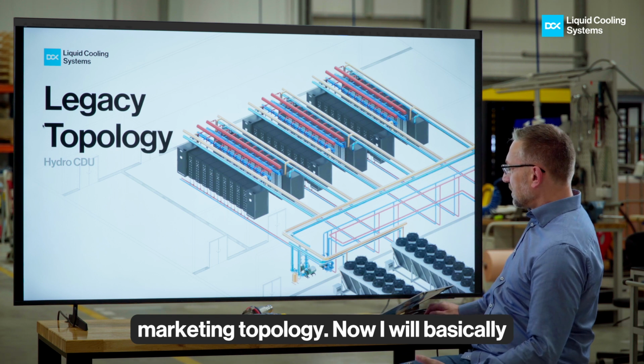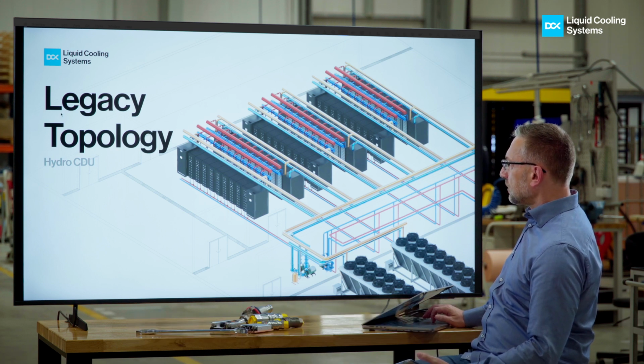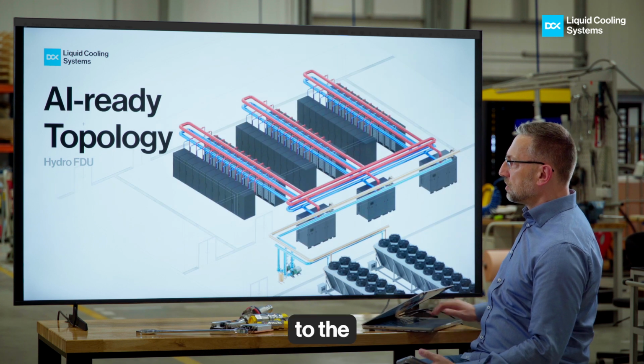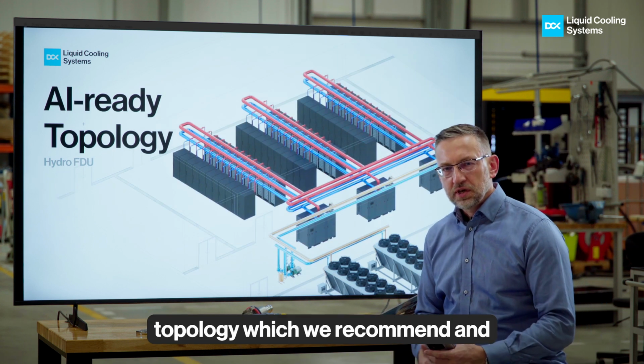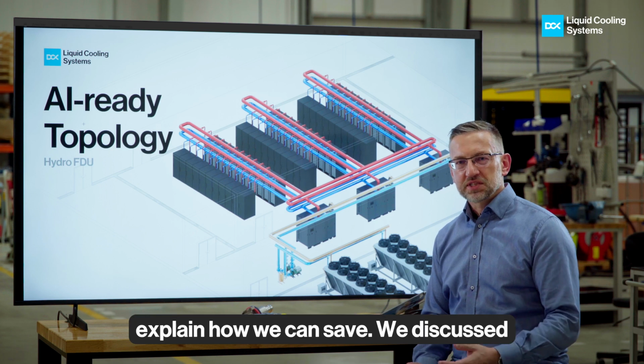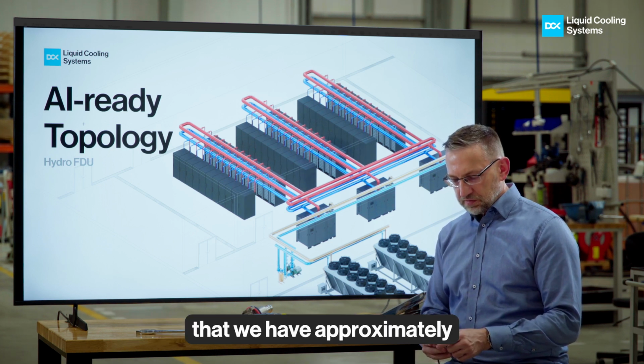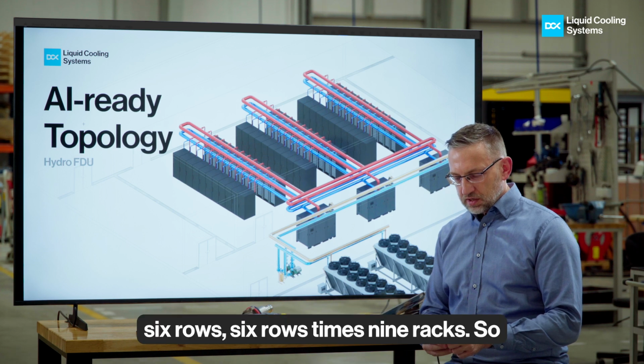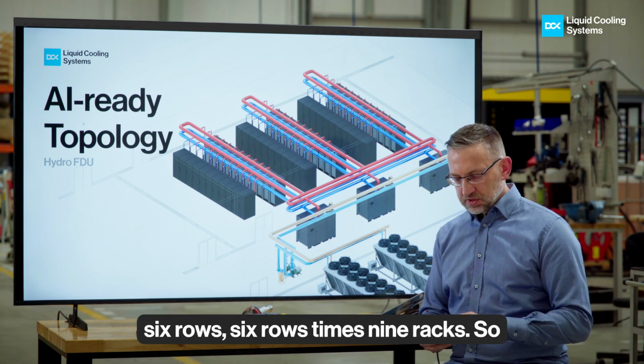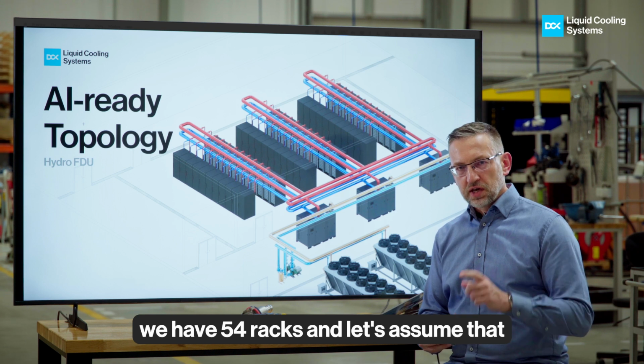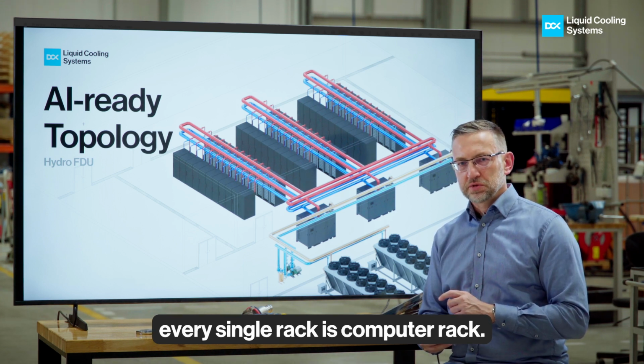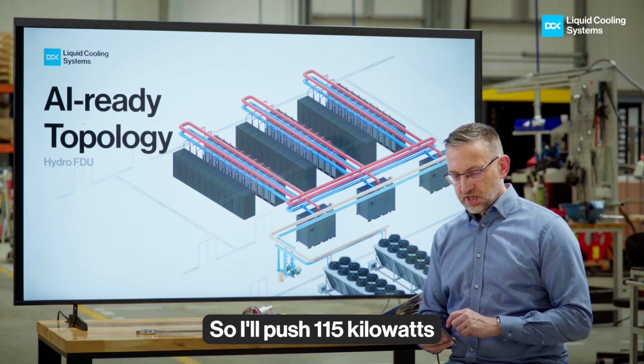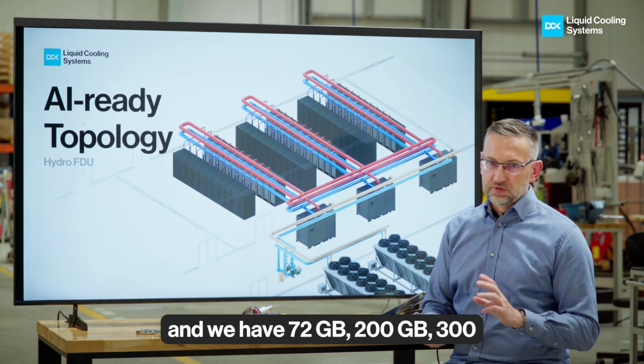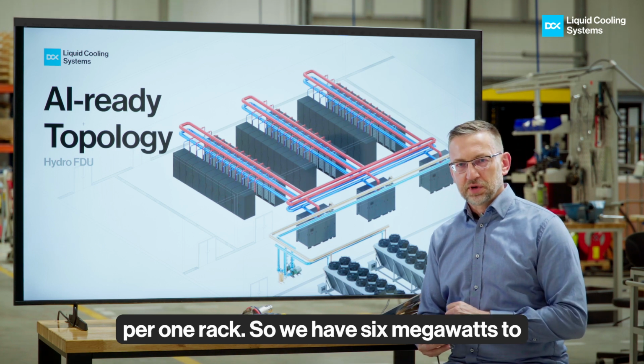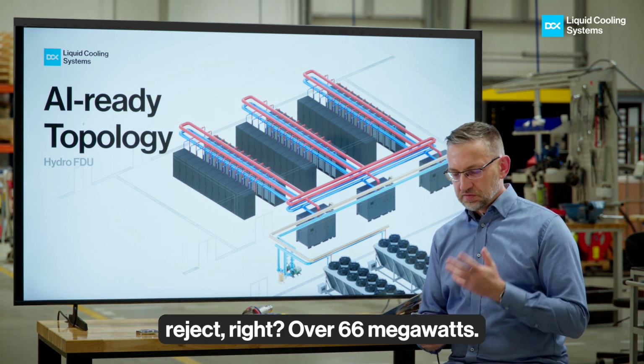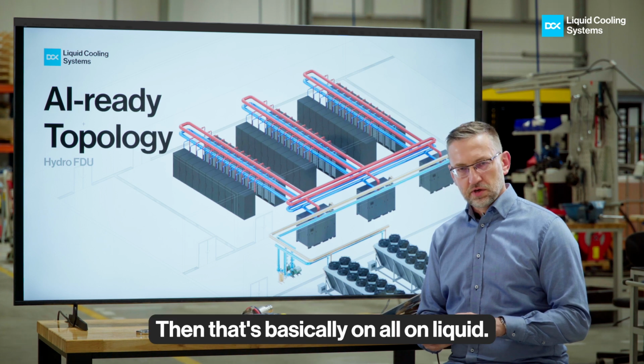Now, I will move on to the topology which we recommend and explain how we can save. We discussed that we have approximately 6 rows times 9 racks. So we have 54 racks. And let's assume that every single rack is a compute rack. So I'll push 115 kilowatts NVL72, GB200, GB300 per rack. So we have 6 megawatts to reject, right? Over 6 megawatts. And that's basically all on liquid.